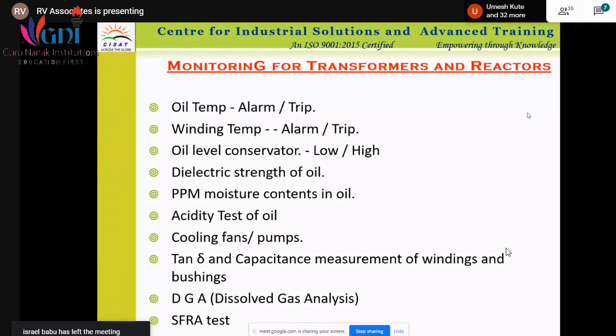Now the insulation system has improved, so you can increase the temperature of the transformer to maybe 100 degrees centigrade. But as temperature rises, the oil parameters also change. So you are taking a risk by raising the operating temperature of the transformer, but that is possible because we are using the vacuum impregnation system for the insulation. Then there is the winding temperature. The same thing, alarm and trip, is there. Because it is winding, 5 more degrees are allowed, so it is 90 to 95 degrees. At 90 it will be an alarm, at 95 it will be a trip.